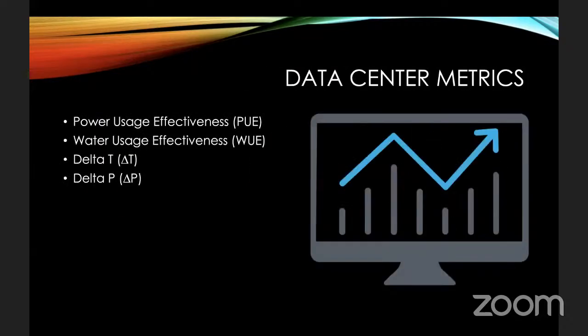So going on to the next slide here, we have some data center metrics. You've probably heard of PUE. It's a bit of a buzzword in the data center industry. That's power usage effectiveness, and that is how efficiently your data center is utilizing its power versus its cooling. You also have water usage effectiveness, which is a ratio of the amount of water used per year versus the amount of kilowatts consumed by the IT equipment. We also then have two values here, which are delta T and delta P. Delta T is a temperature difference and delta P is a pressure difference. I'm going to go into more detail on each of these in the following slides.